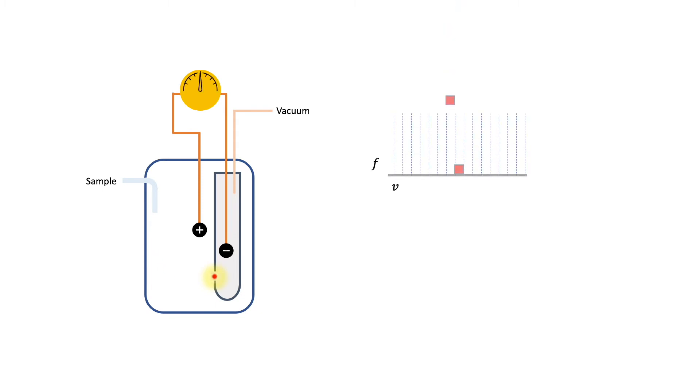This change in impedance is proportional to the volume of the red cell passing through it. The pulses and the size of the pulse wave is integrated and fed into a computer which can plot the data on a histogram.